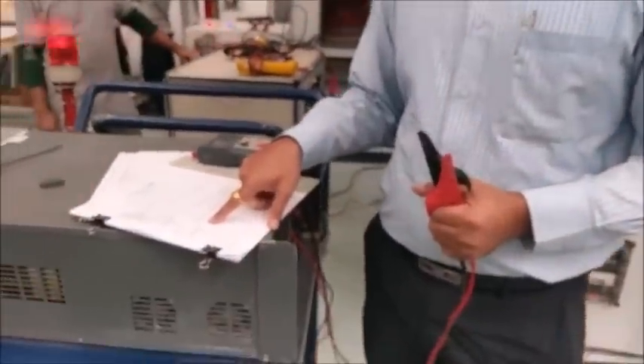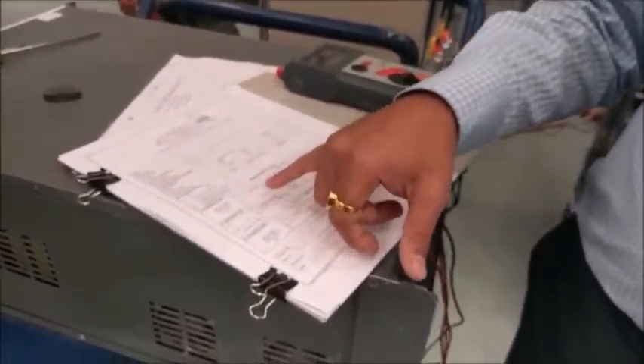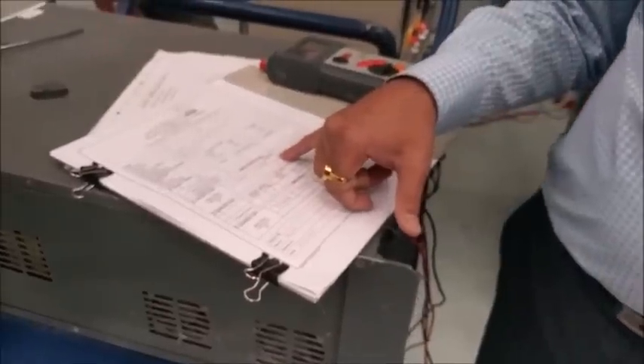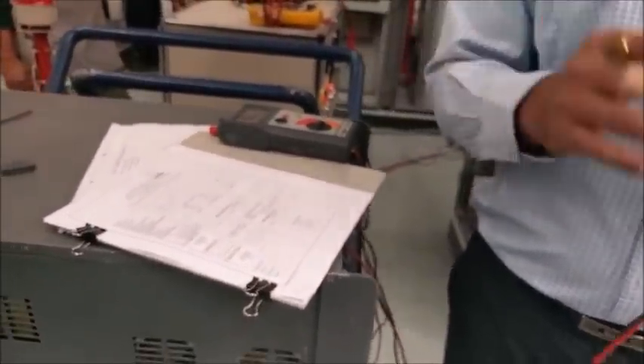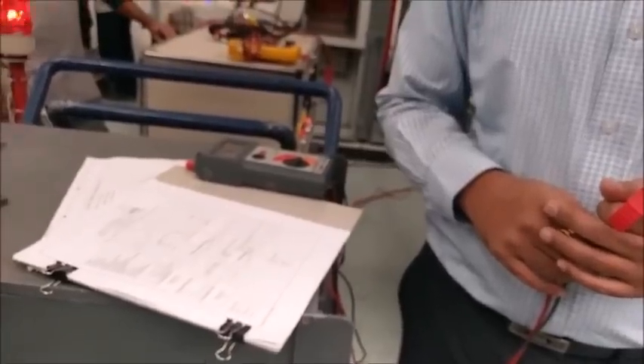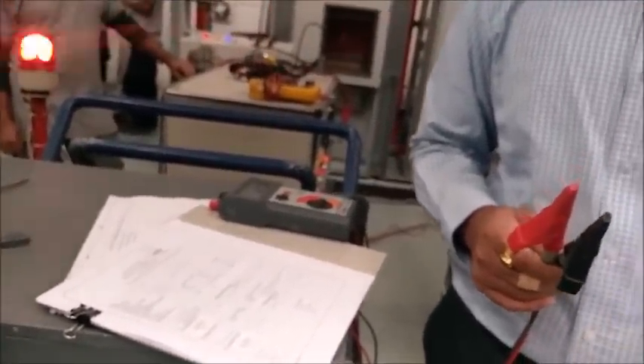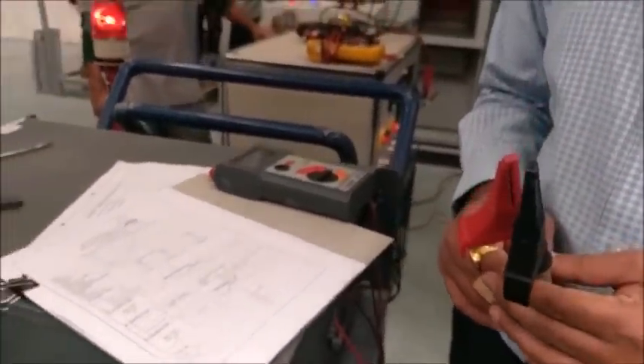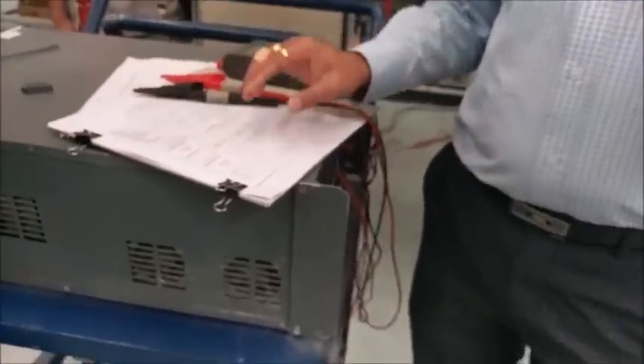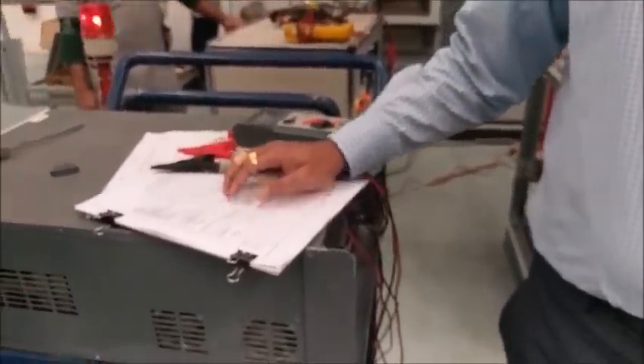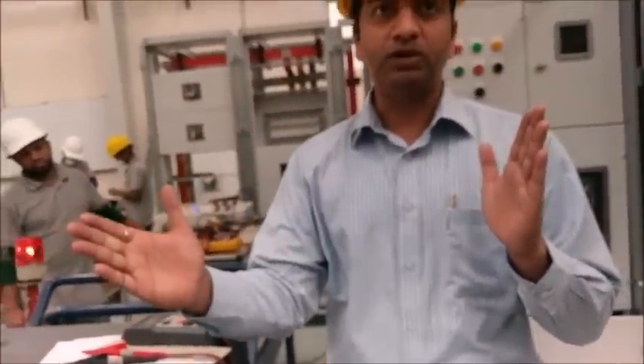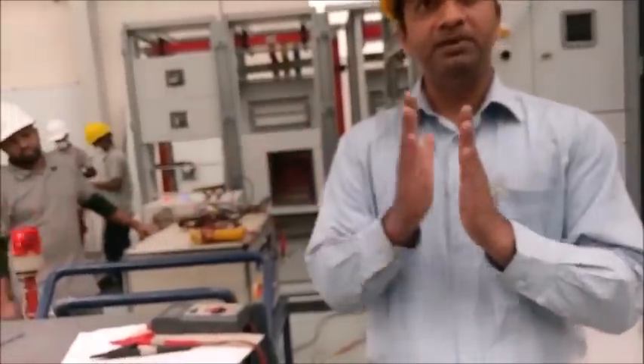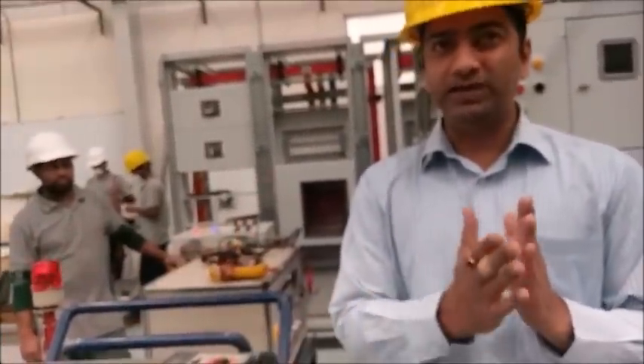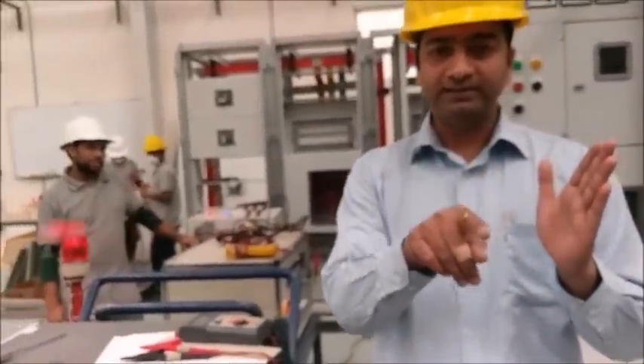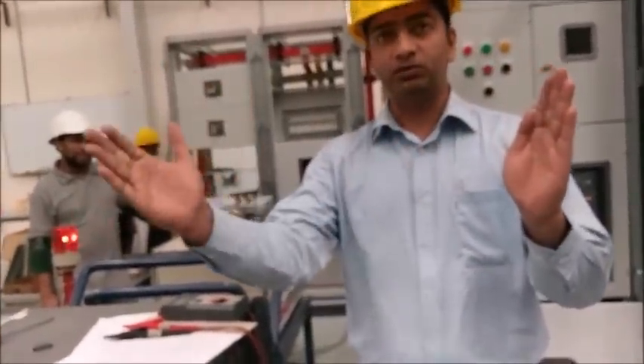And what we are doing is, again a similar case. We have to short the R, Y, B phases, and with respect to neutral we provide the high voltage. This is for the dielectric test. Individually also we can perform: R phase with respect to neutral, Y phase with respect to neutral, and B phase with respect to neutral. Or we can short the 3 phases and check with respect to neutral.